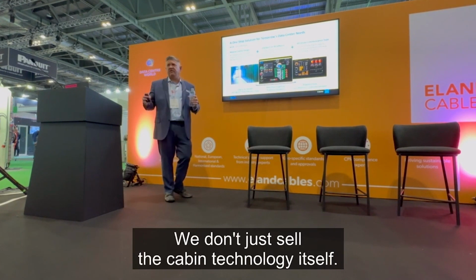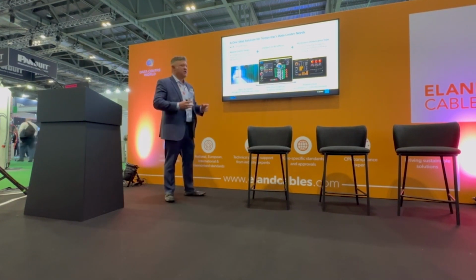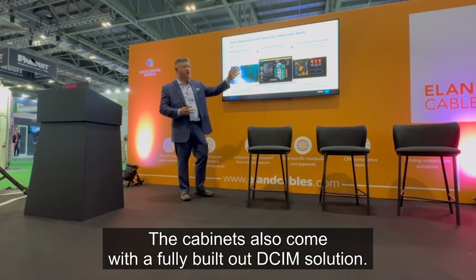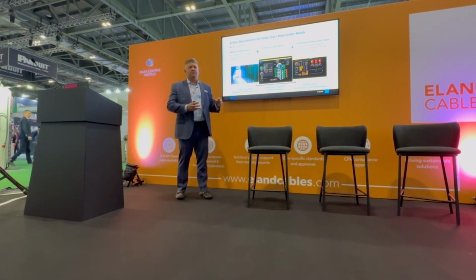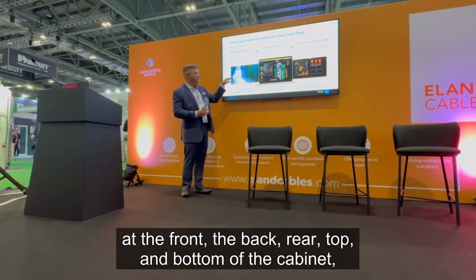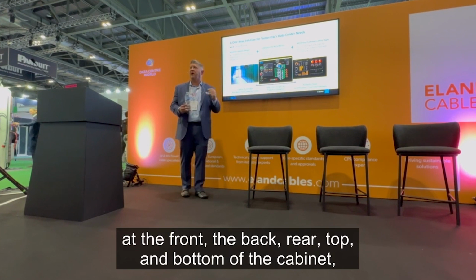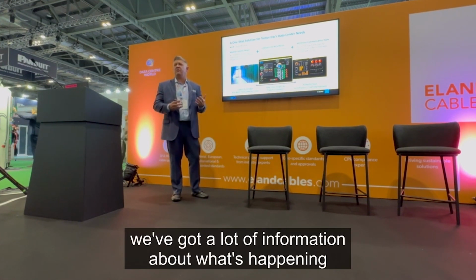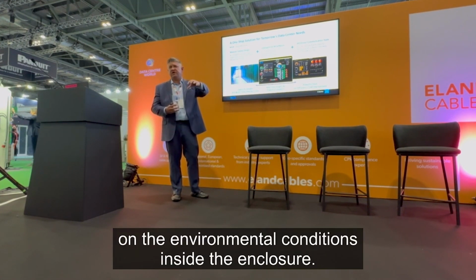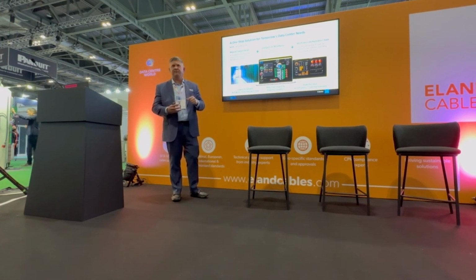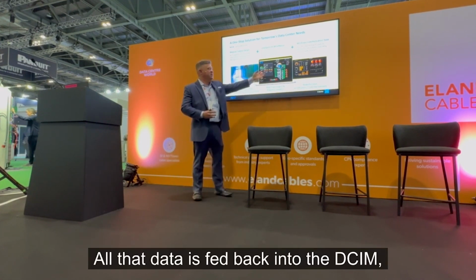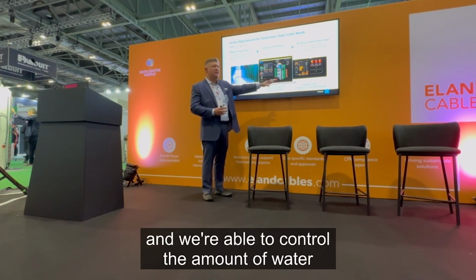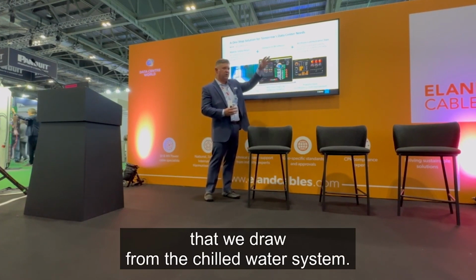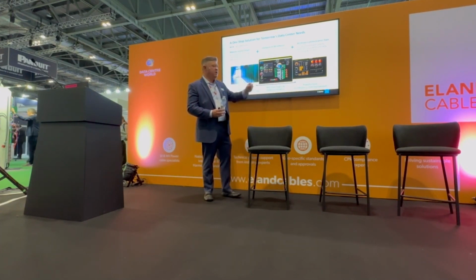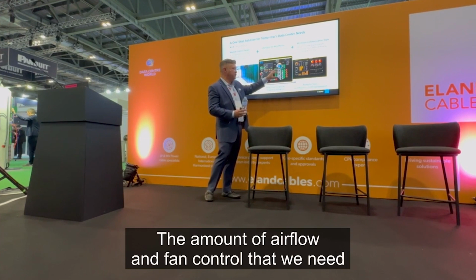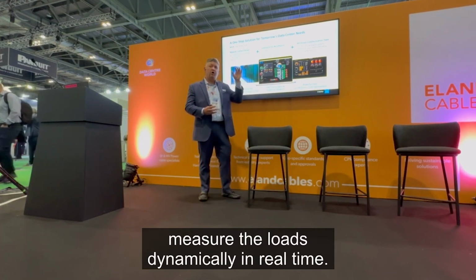We don't just sell the cabinet technology itself. The cabinets also come with a fully built out DCIM solution. Because we're monitoring temperature at the front, back, rear, top, and bottom of the cabinet, we've got a lot of information about the environmental conditions inside the enclosure.